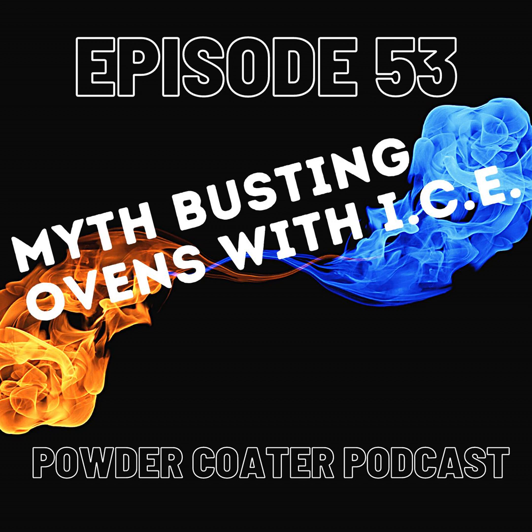I've never really heard of any real issues. Even if you had a little bit of moisture in the propane, with the temperatures you're running, you're going to boil all that off. Now there may be, and I've only seen this maybe 3 different times in 40 years, where sometimes in a process system, they'll use a combination dry off and cure. And they'll run the washed parts in the same atmosphere as the color. Like I said, 3 times I've seen a slight blushing of the finished color because of the additional moisture in the oven from the wet parts coming in.